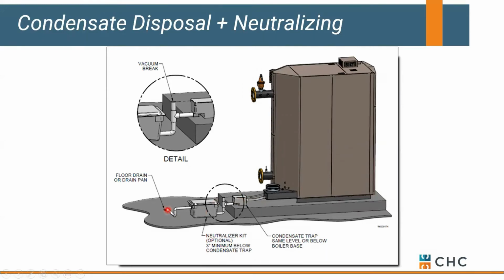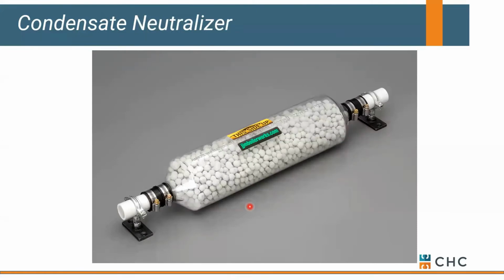and then to drain. Okay, that condensate that's coming out with low return temperatures is acidic. That's usually why they have a stainless steel collection pan here. It has a pH from 2 to 5, so it's pretty aggressive. So you want to deal with that properly. You want to make sure you have a good pitch to drain, proper elevation. You also want to make sure you have some type of neutralizer that allows you to take that acid and turn it back into a neutral solution before you dump it down the drain.